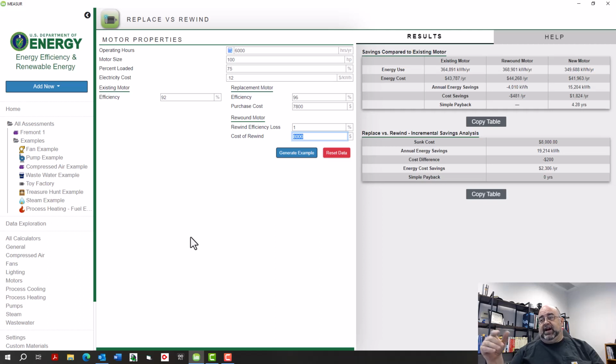So let's say we're going in and we got El Cheapo down the street. Because we know it's El Cheapo and he's not paying attention to his EASA requirements, we're going to say, because I saw this video on LinkedIn, everybody was going, that's a great rewind. Oh boy, they're doing so great. And while we're watching, somebody with a metal ball peen hammer hits the outside race of the bearings to get it on. So let's say it's a 5% loss, and that's being generous. So it's going to be a 5% efficiency loss.